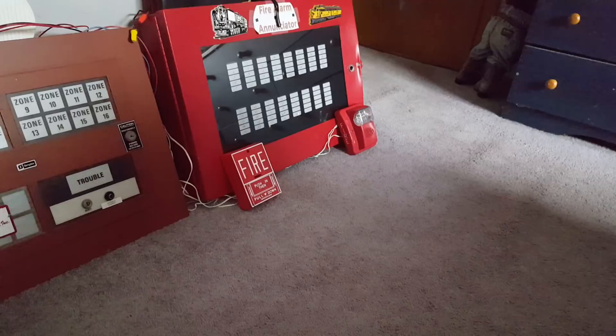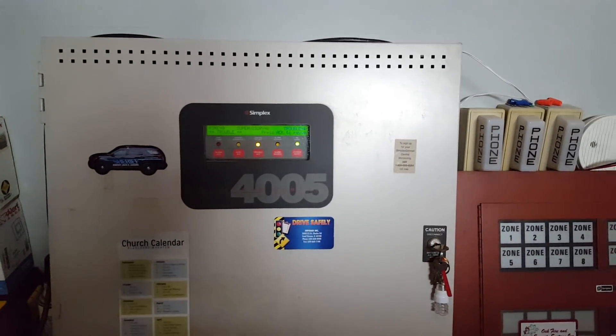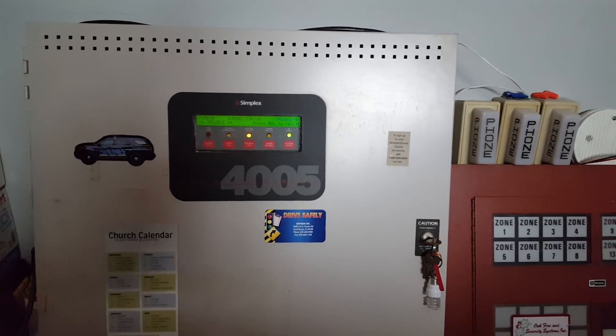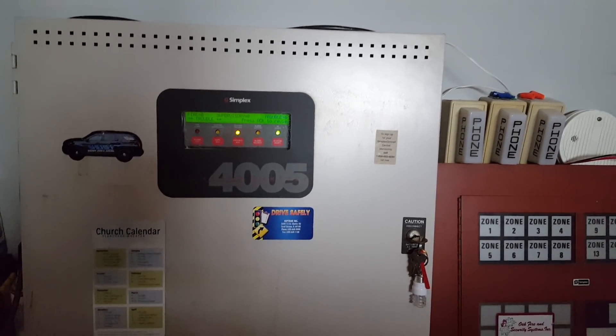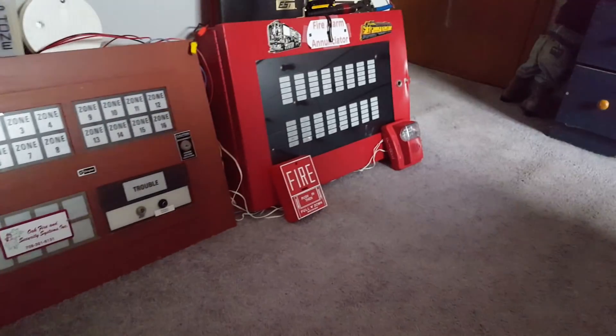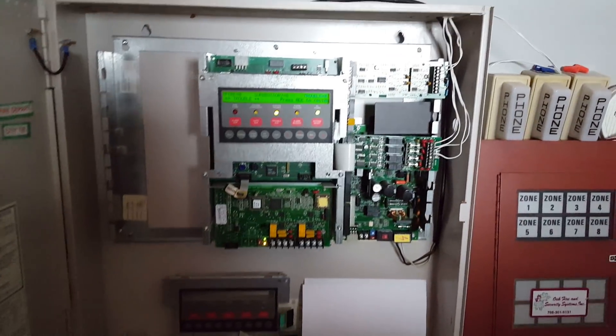As far as settings go, I've got the Commander 2 on Code 3 Chime, and the panel is putting out a continuous signal on that NAC. So the alarm is coding itself, and then the strobe is on NAC 2, so that will continue flashing until the system is reset. Nothing has changed with the system, so everything on the panel is the same.